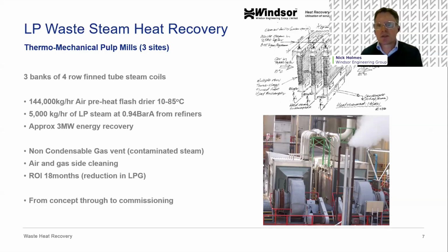So we came up with some concepts, and those concepts turned into sort of feasibility, and then all the way through to a turnkey installation over time. But again, a significant amount of energy recovered, 3 megawatts from very low grade steam at about 110 degrees, I think, just under 1 bar. Quite a complex project because there was some contamination both in the steam, and it was quite a difficult site with dust fibers. So the solution needed to accommodate both of those.